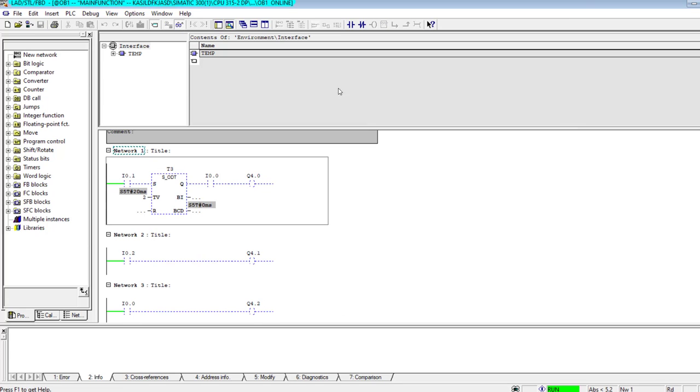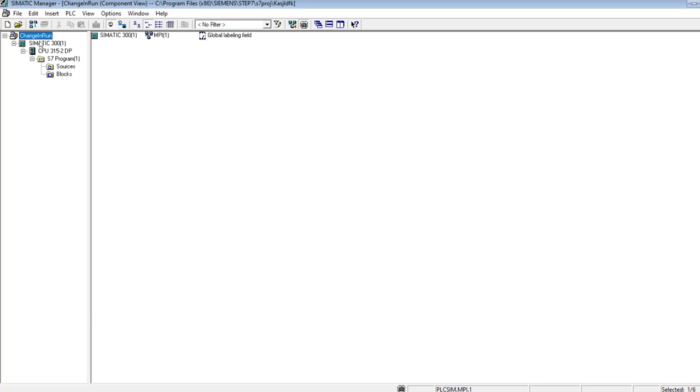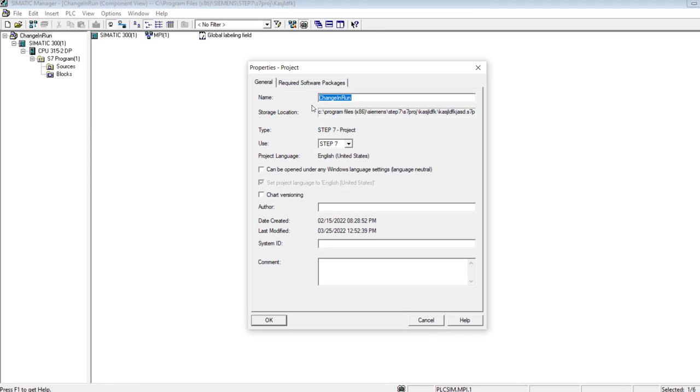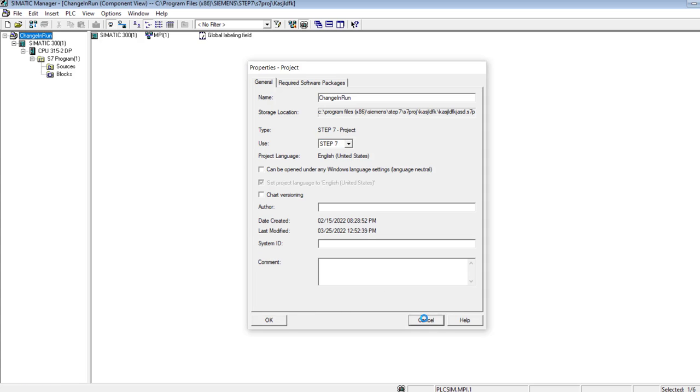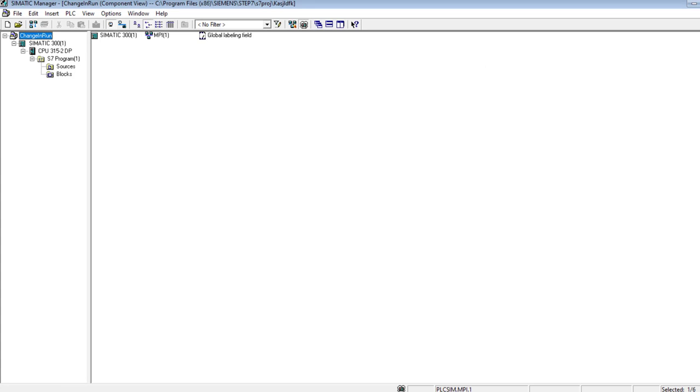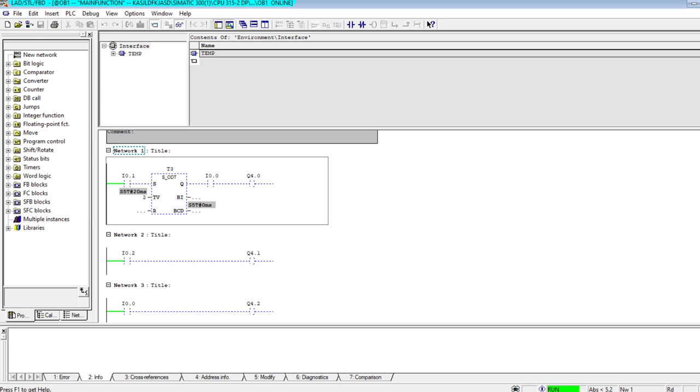And this is how I change my online PLC program. I have made online changes. So this is the simple trick. What we learned: click over here, this is the first tip, object properties. You will have to change it from PCS 7 to Step 7. Then you go to the OB1 and make the necessary changes.